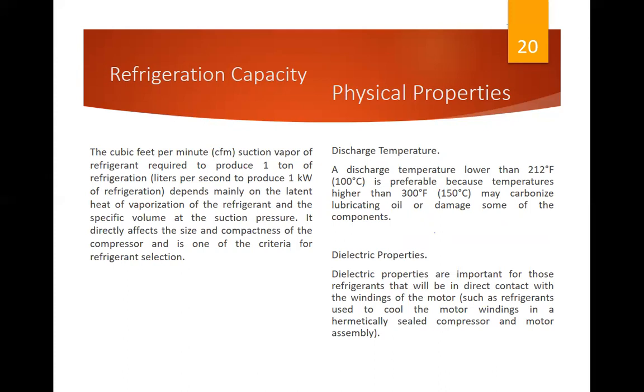Next, physical properties. Discharge temperature. A discharge temperature lower than 200 Fahrenheit or 100 C is preferable because temperatures higher than 300 Fahrenheit or 150 C may carbonize lubricating oil or damage some of the components. The dielectric properties are important for those refrigerants that will be in direct contact with the windings of the motor, such as refrigerant used to cool the motor winding, hermetically sealed compressor, and motor assembly.